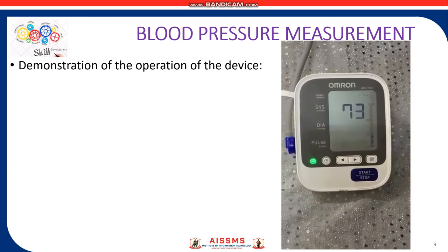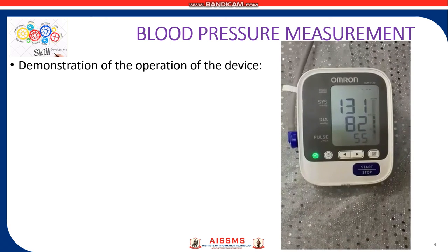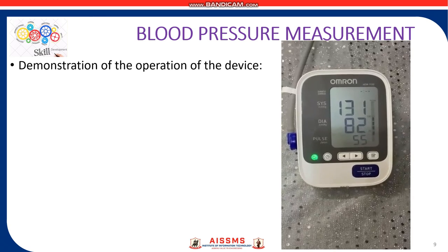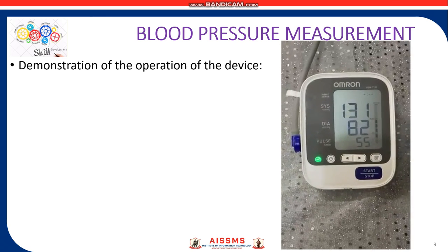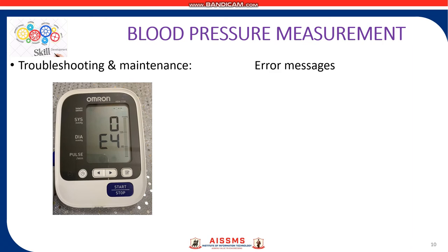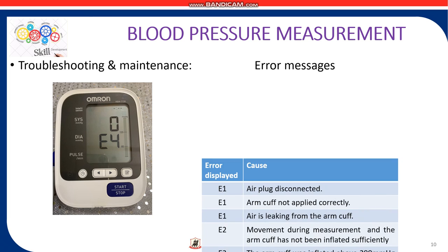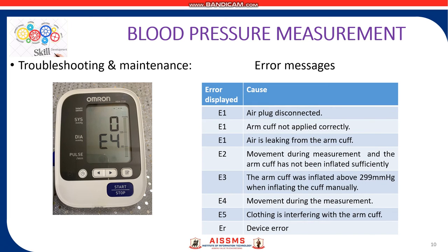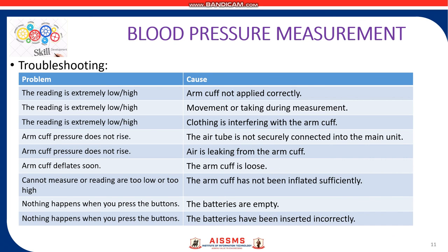This automatic blood pressure monitoring device requires four AAA batteries to operate. The troubleshooting and maintenance of the device includes certain error messages that are displayed, ranging from E1 up to E5 and ER, and their possible causes are listed in the table. Some problems, their root causes, and corresponding solutions are also listed in the troubleshooting table shown.